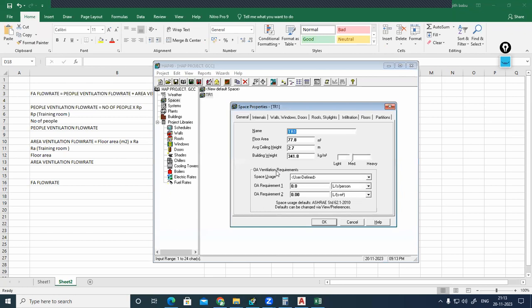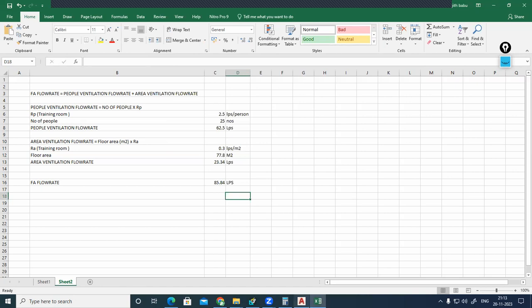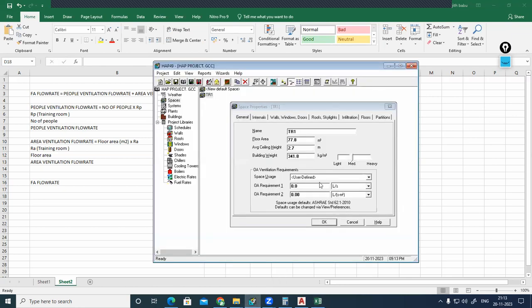We can select this one, the TR1 space. Under the outside air ventilation section, space usage, you can select user defined. In this section, I am not providing any value. Outside air requirement, I am not providing any. Out of these two, anywhere you can provide. Outside air requirement one, instead of liter per second per person, I am selecting liter per second value. How much is it in liter per second? 85.84. 85.84, you can round into 86. Even if you are not rounding, the software will round it.